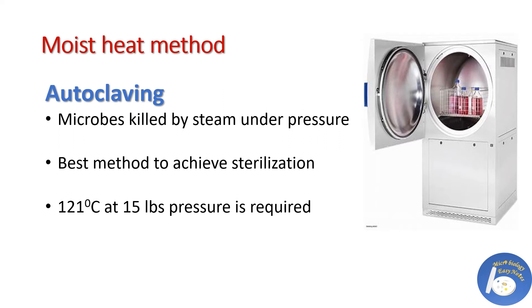Autoclaving is the best method to achieve complete sterilization. In an autoclave, steam is generated under high pressure in an airtight chamber; in this condition, all forms of microbial life are killed. 121 degrees Celsius and 15 lbs per square inch pressure is generally required to achieve sterilization. This method is used to sterilize various types of media and liquids, and also to dispose of or destroy used materials. For details on the principle, discovery, procedure, types, and precautions of autoclaving, check the description box below.